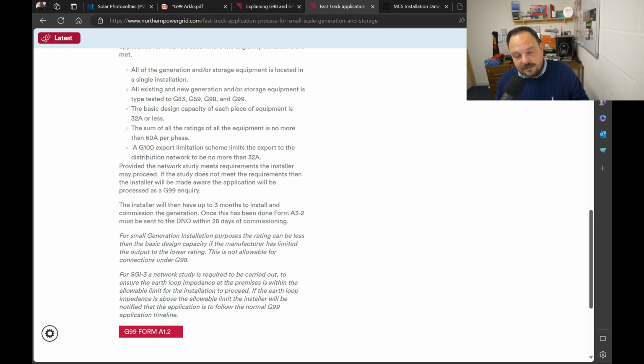You have 3 months to install and commission the generation once your form is approved, and that must be sent to the DNO within 28 days of commissioning. There are rules around all that, and I think they give a fairly short window because they don't want to block slots a neighbour might want. There's a certain amount of capacity the DNO can accept onto the network, and if you're sat on a fast-track G99 for a year holding that space, it denies someone else who may be ready to proceed. So they've narrowed down those timescales.